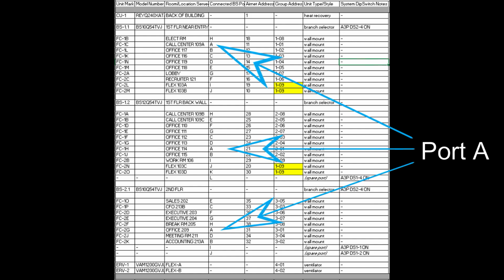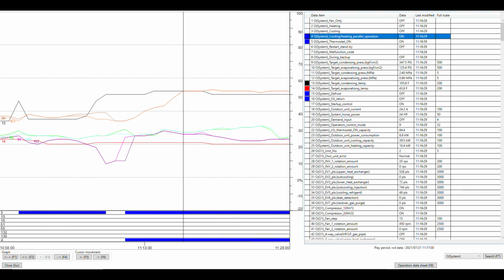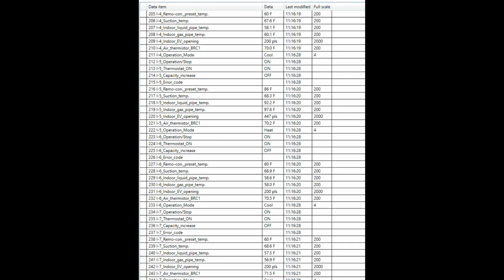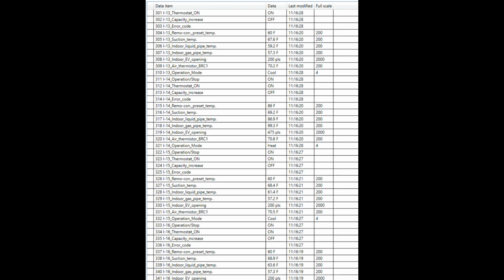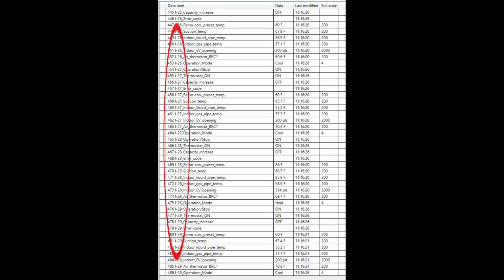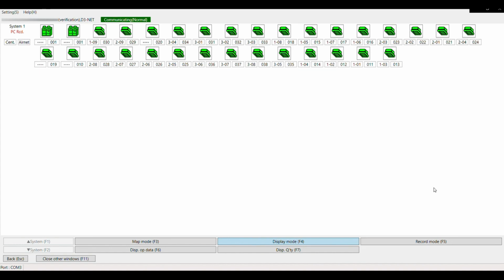The system will take about 5 minutes to change over, and a few extra minutes since this is the first set of ports going to heat mode before the indoor units actually start heating. You'll notice that each indoor unit has data shown in segments, first I1, then I2, then I3, all the way down to I29. These I numbers are the icon numbers shown back on the network map. And you may have noticed that each unit was pulled into the network in what seems like a totally random order.